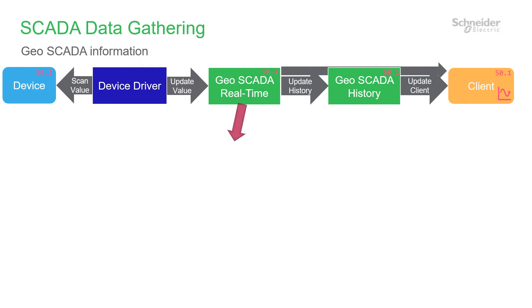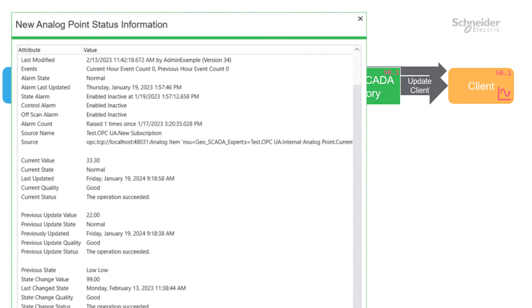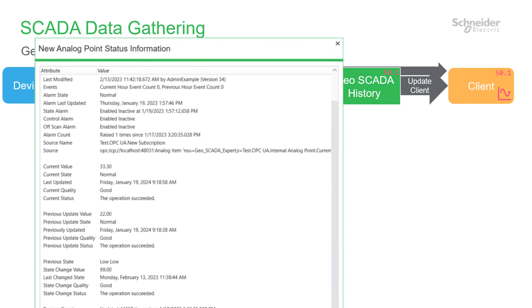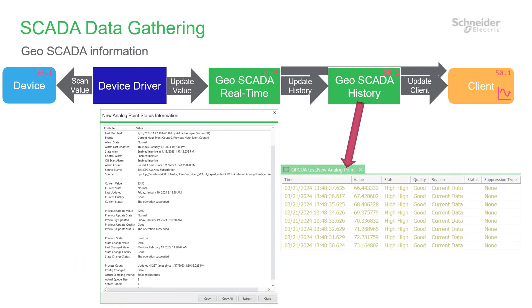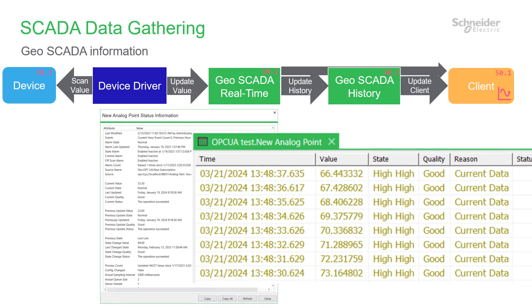Added to this, GeoScada does more work than a clockwork SCADA system. GeoScada extracts and stores more information because it supports RTUs with time logged data. You can see that any individual data update includes previous value updates, quality, current and previous states, process and alarm information. And the historian also stores more than just values — it includes reason data and supports controlled updates.